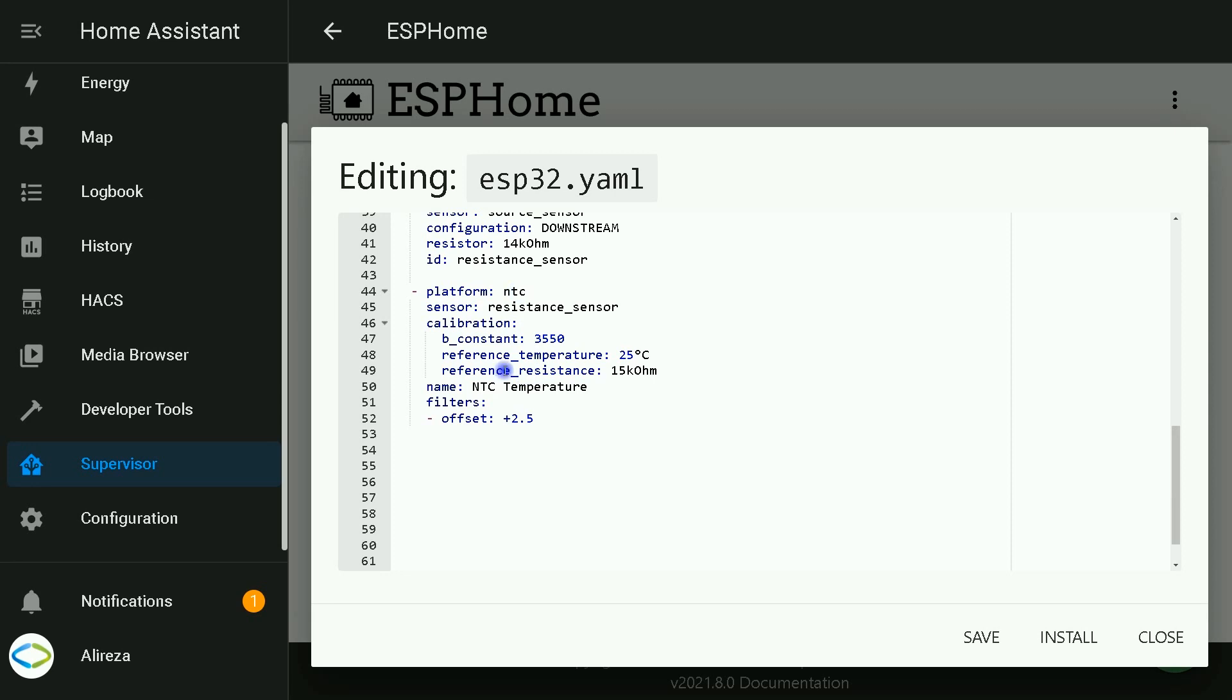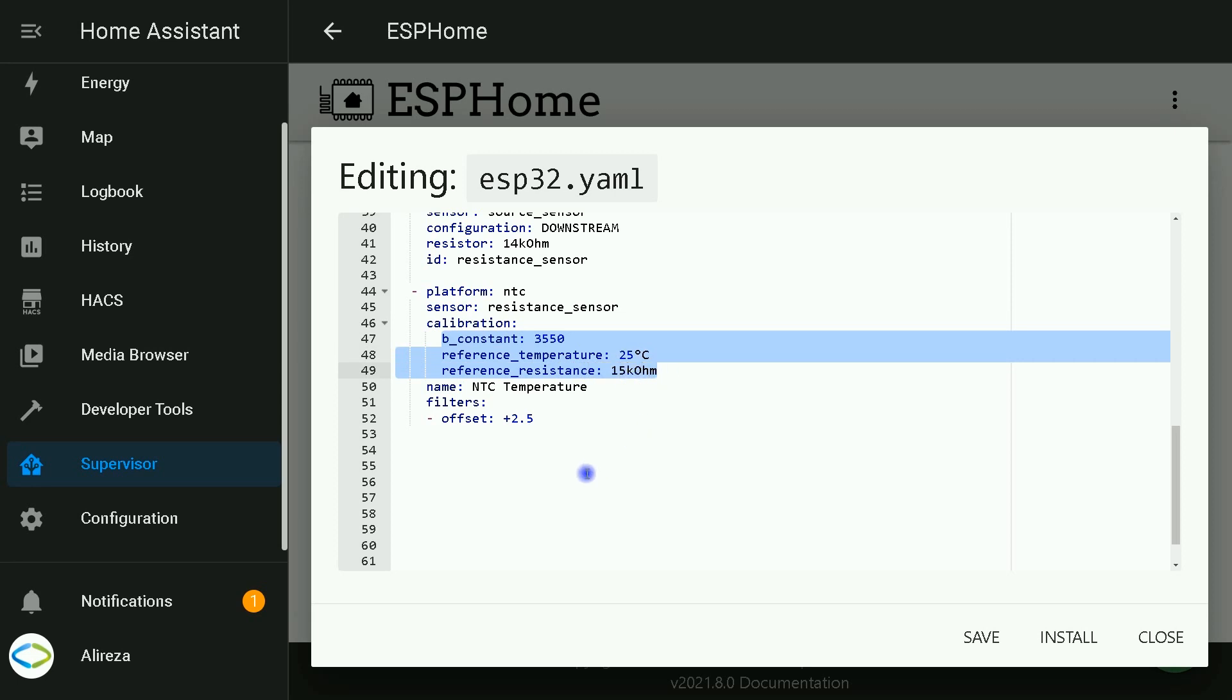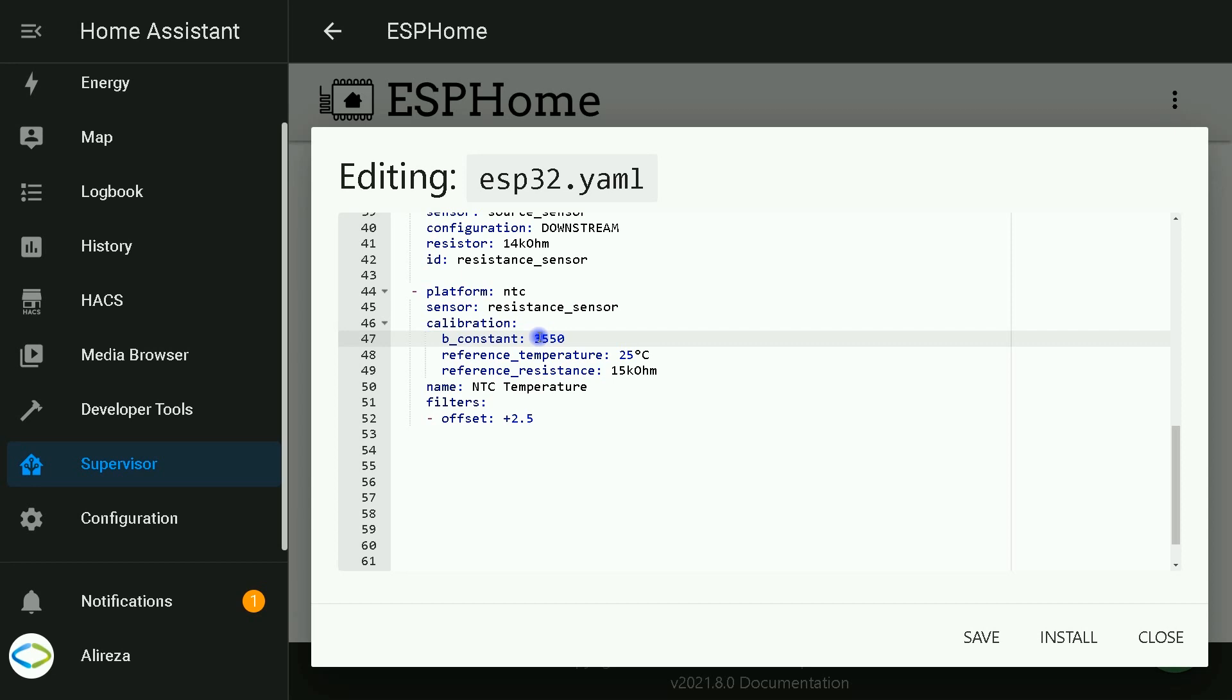In NTC section, in calibration, there is a B constant, reference temperature, and reference resistance. You can find out about these numbers by looking at the data sheet of your thermistor. If you don't have access to data sheet or want to calculate these values yourself, you have to first measure three resistance values at different temperatures. Heat or cool the NTC to three different temperatures - best if temperatures are far apart - and write down the resistance readings at those temperatures.